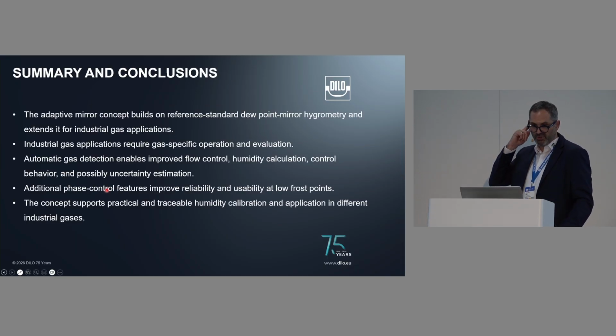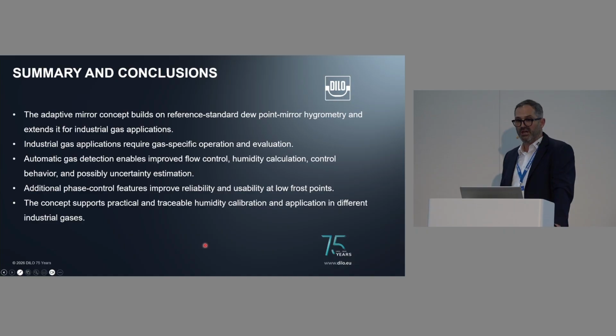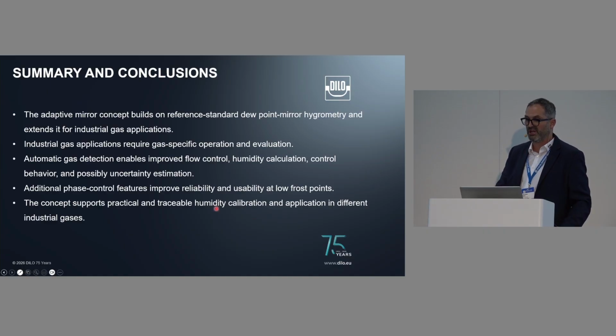So now I come to my summary and the conclusions. Our adaptive mirror concept builds upon reference standard dew point hygrometry and extends it for industrial gas applications. Industrial gas applications require gas-specific operation and evaluation, and automatic gas detection enables improved flow control, humidity calculation, control behavior, and possibly also gas-specific uncertainty estimations on the device itself. Our additional phase control features improve the reliability and the usability at low frost points. And the concept supports practical and traceable humidity calibration and application in different industrial gases.